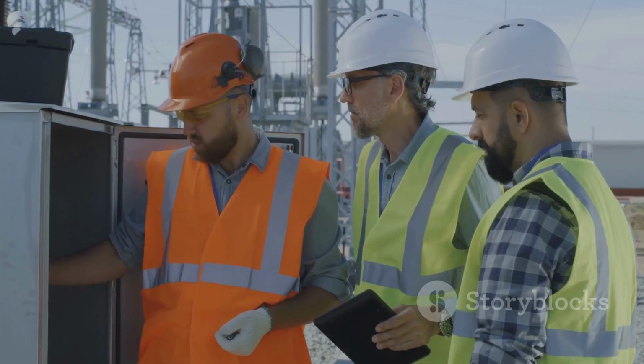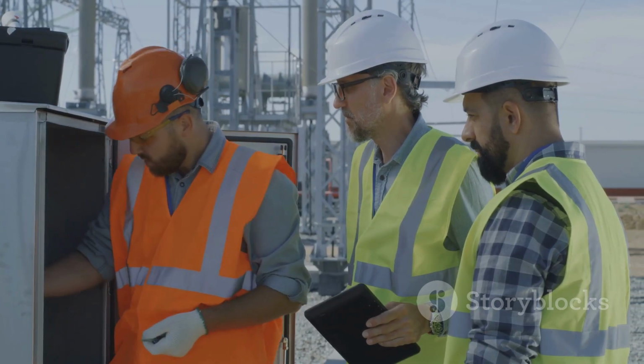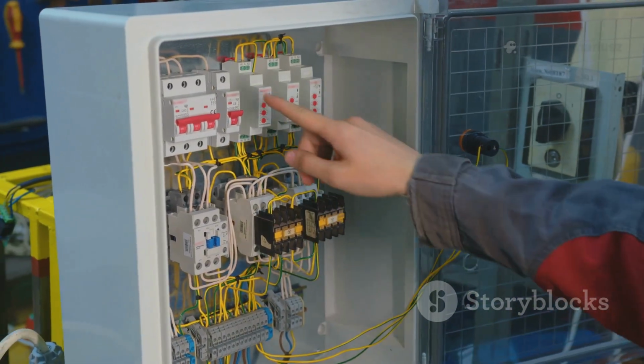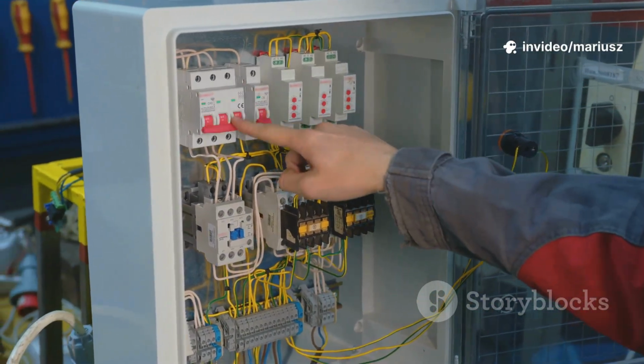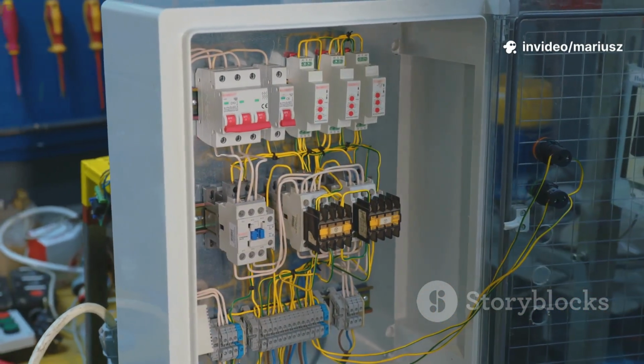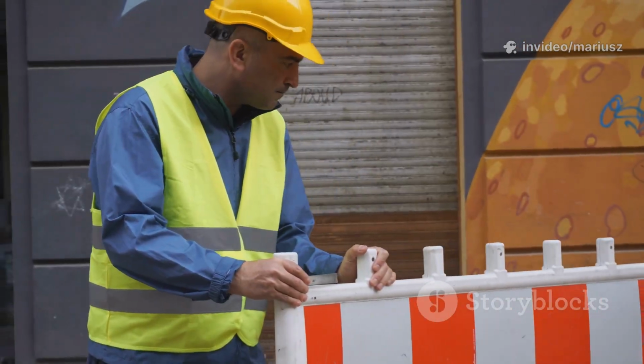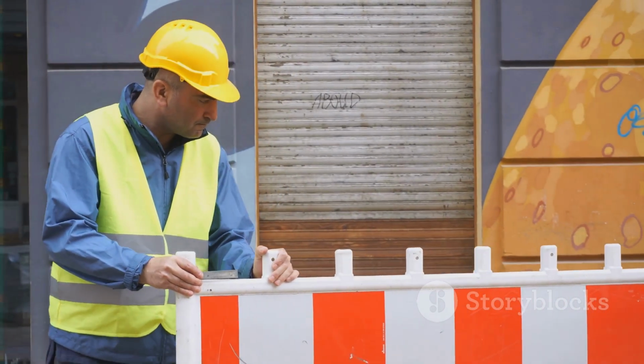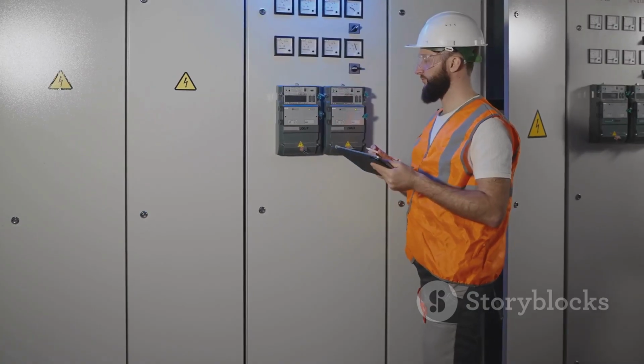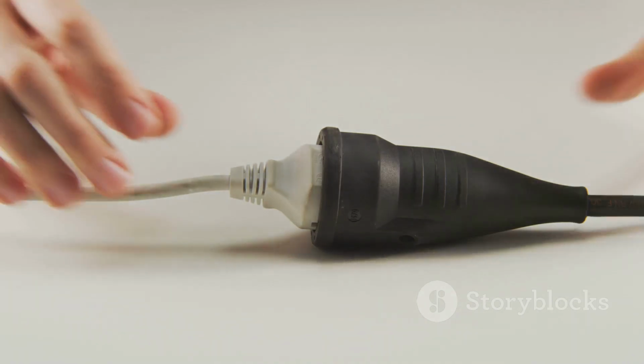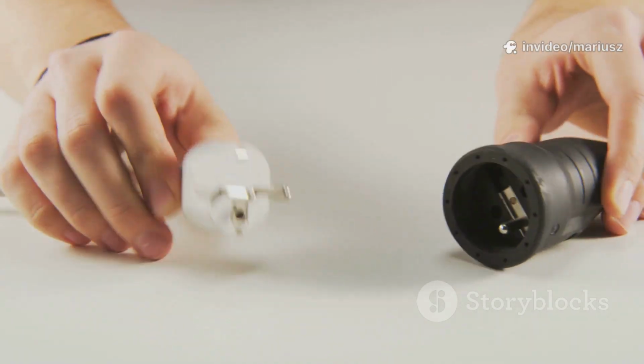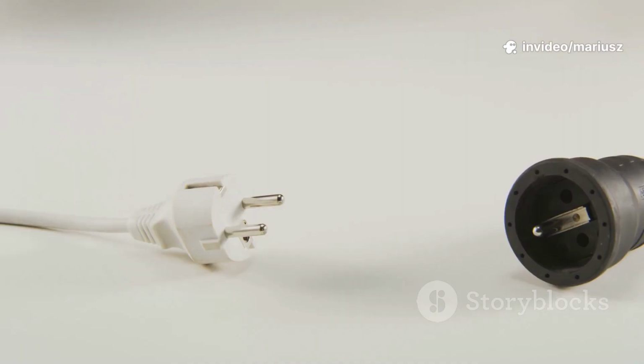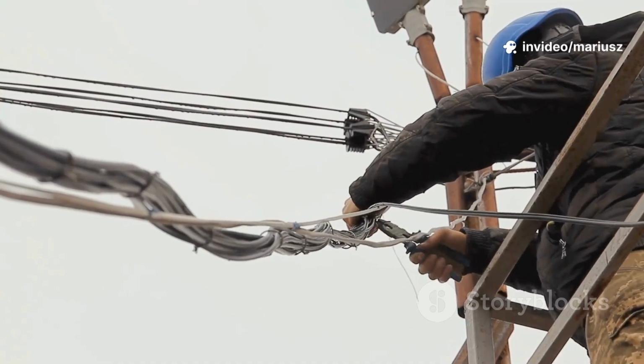This process of isolation is the first critical step. We are physically disconnecting the motor from its power source in a way that is secure, visible, and under strict control. It's about creating a physical barrier, not just a procedural one. But what if there's stored energy? A disconnected cable can still hold a dangerous electrical charge, much like a camera flash capacitor. That's where the next step comes in.